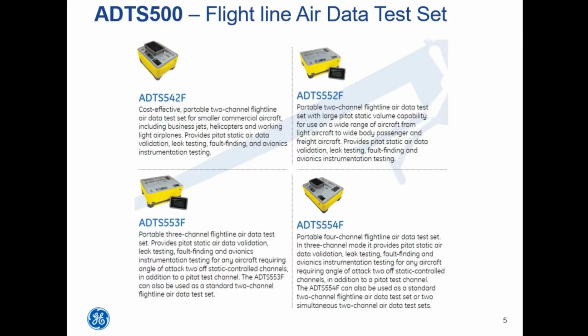Okay, so the 552 has 5,000 hours of pump operation before it requires maintenance, which is a hell of a long time, and it can control into larger volumes, so no problems there or considerations to take into account. If you think about extending your calibration to 18 months, that's a huge savings in cost over the life of the instrument. Incidentally, the 542 has an option to extend to 15 months, and the 552 starts at 15 months as standard.